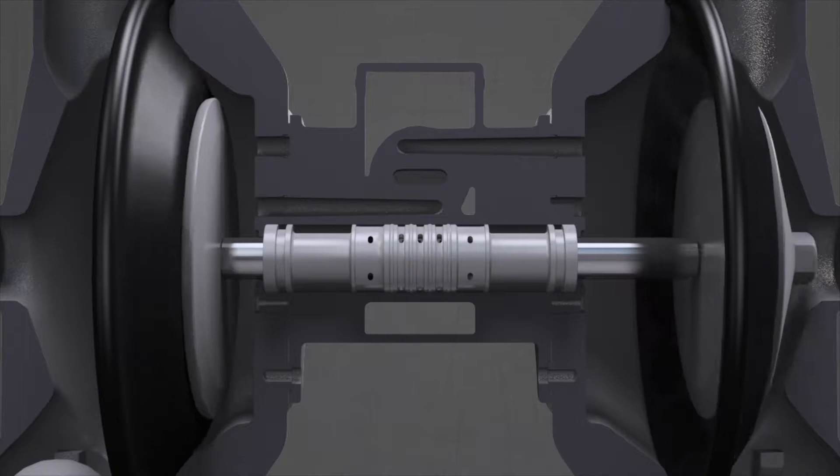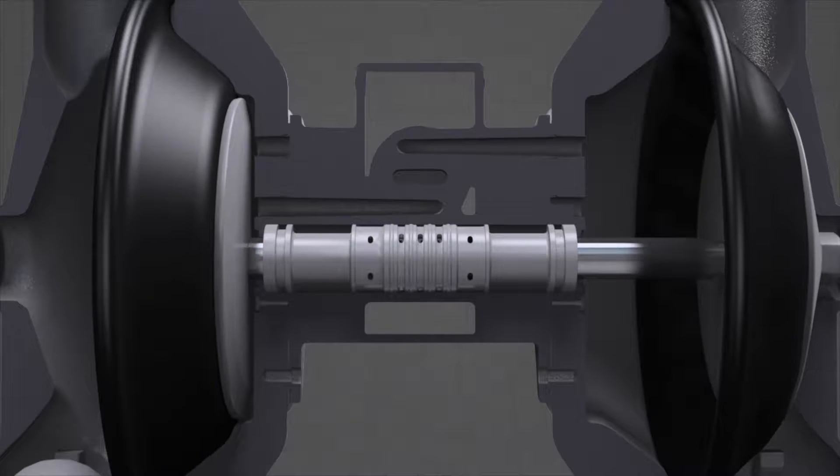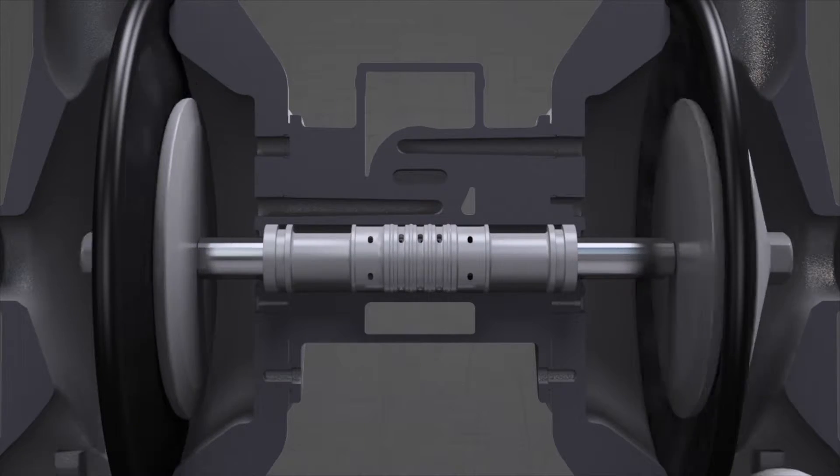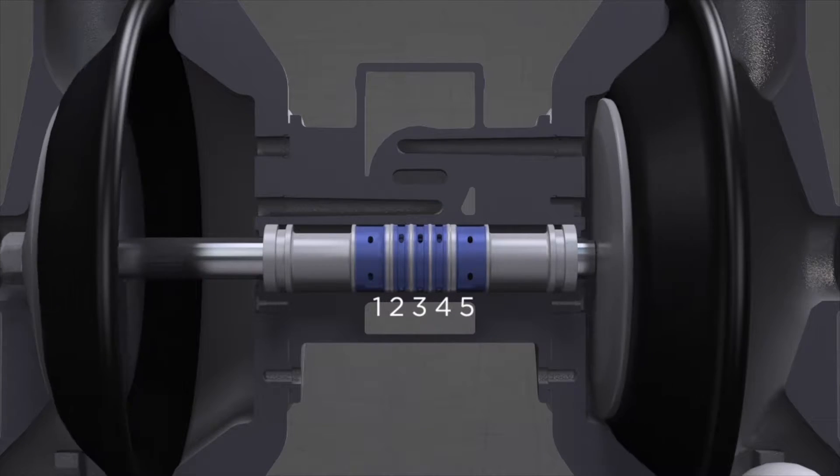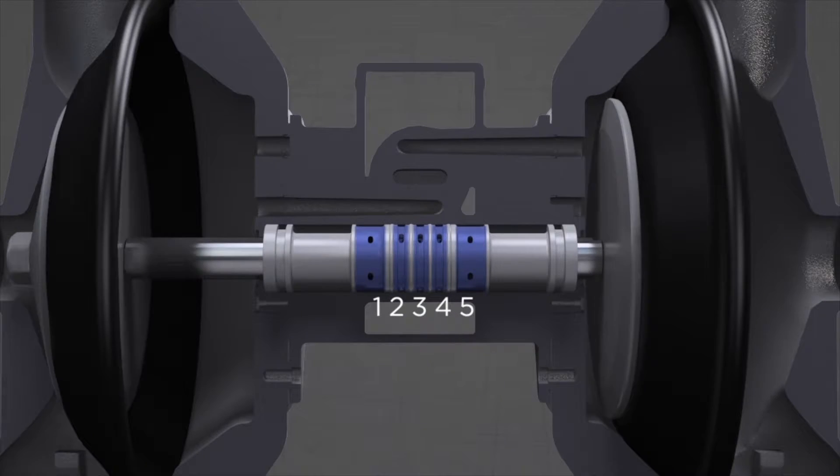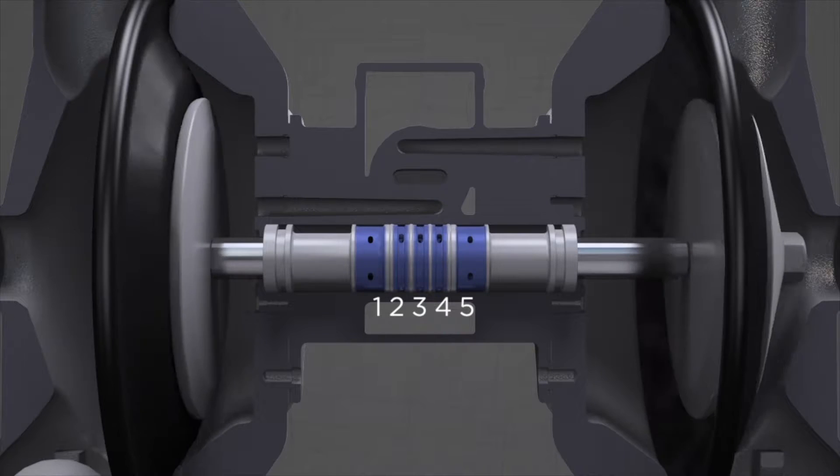The pilot air valve directs the air that moves the main air valve. It is constructed of five separate chambers and a central rod that moves side to side due to the diaphragm pressurizations.